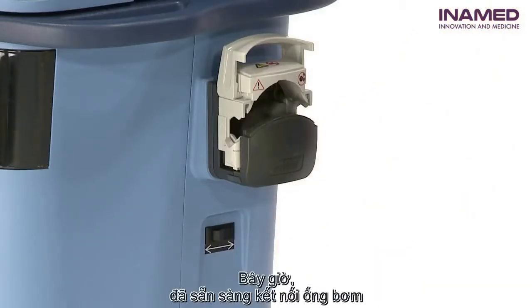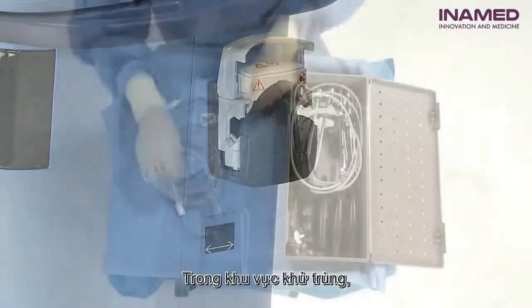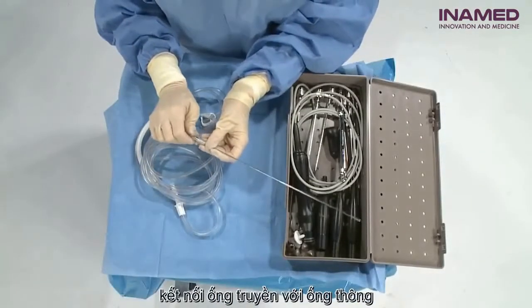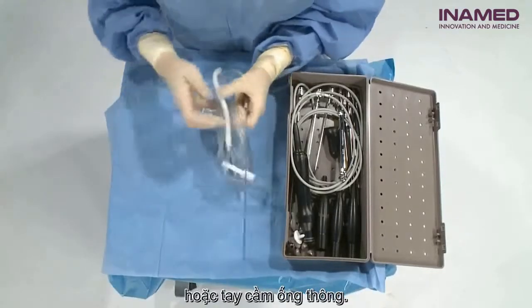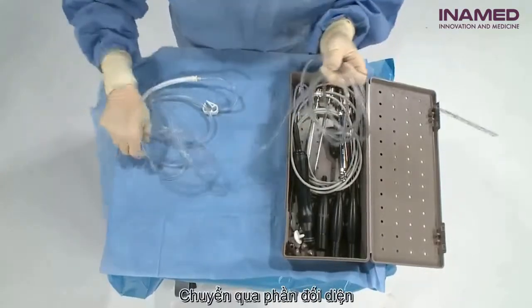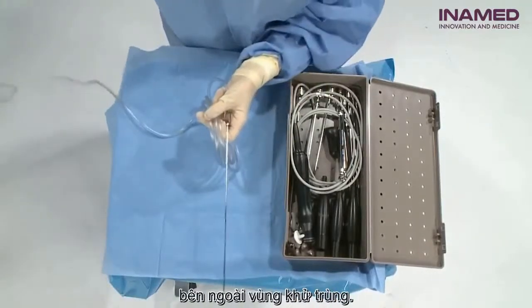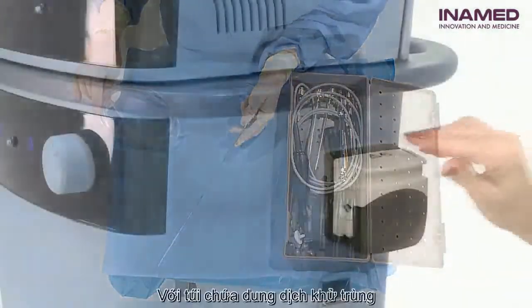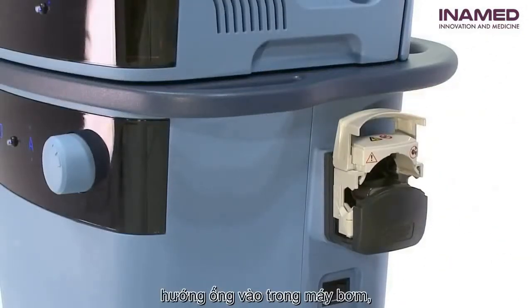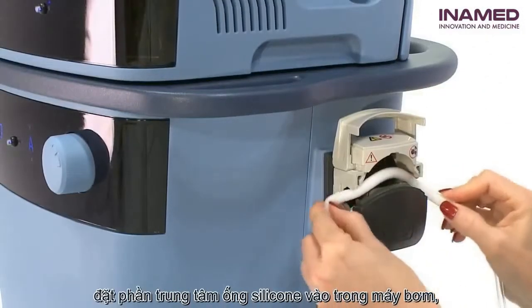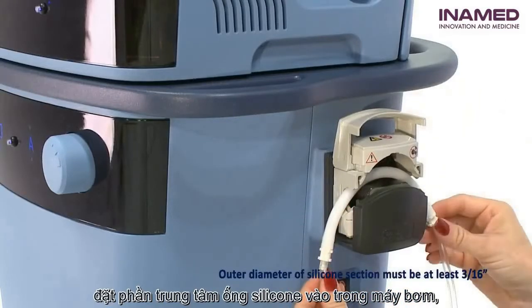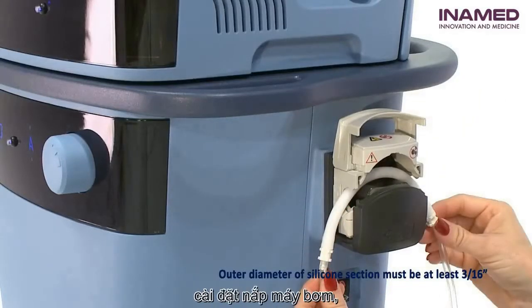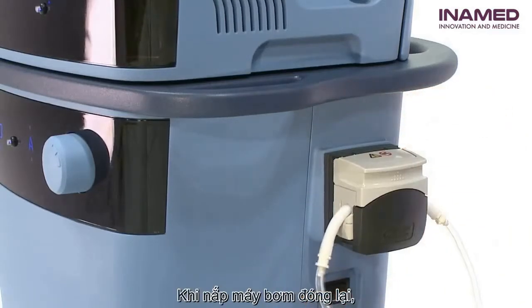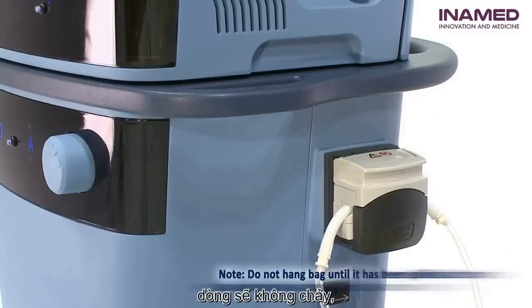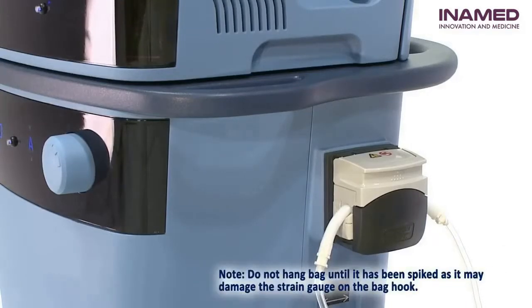Now you are ready to connect the infiltration tubing. In the sterile field, connect the infiltration tubing to the infiltration cannula or infiltration cannula handle. Pass the opposite end, the end with the bag spike, out of the sterile field. With the infiltration tubing bag spike toward the sterile fluid bag, center the silicone section of the infiltration tubing inside the pump head. Align it with the grooves at the entrance and exit of the pump head. Close the pump head. With the pump head closed, fluid will not flow unless you depress the foot switch.